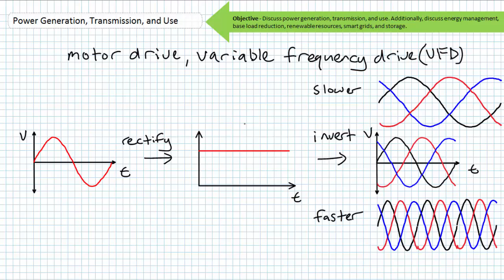On the input side, single-phase AC is rectified to DC, and then DC is inverted into three separate single-phase AC waveforms with a relative phase shift between them. By making the cyclical shift occur at a more rapid rate, i.e. by increasing the frequency, the motor turns faster. By decreasing the frequency, the motor turns slower.